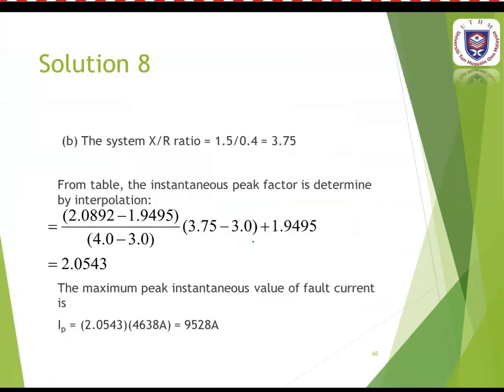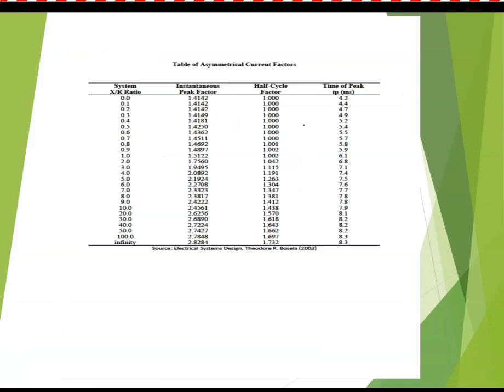To identify the instantaneous peak factor, first calculate the X/R ratio: X divided by R gives 3.75. The instantaneous peak factor is found using the asymmetrical current factor table. Since X/R = 3.75, look in the range between 3 and 4 in the table.